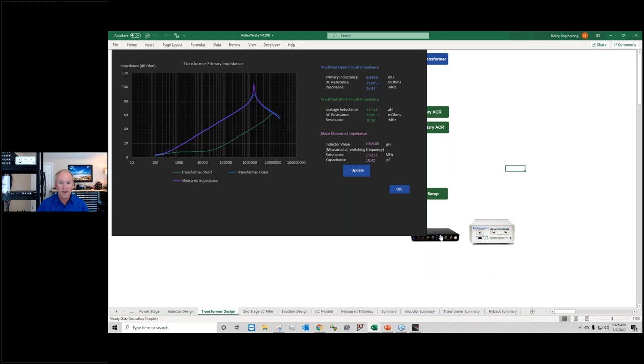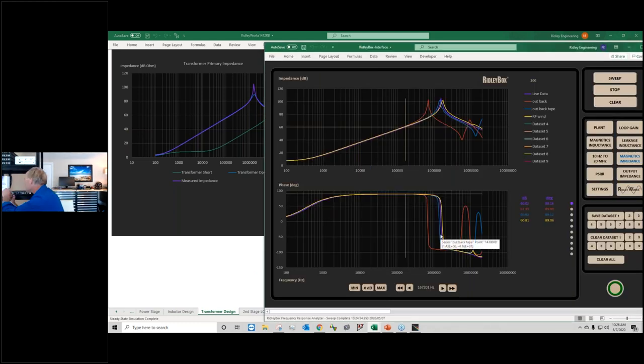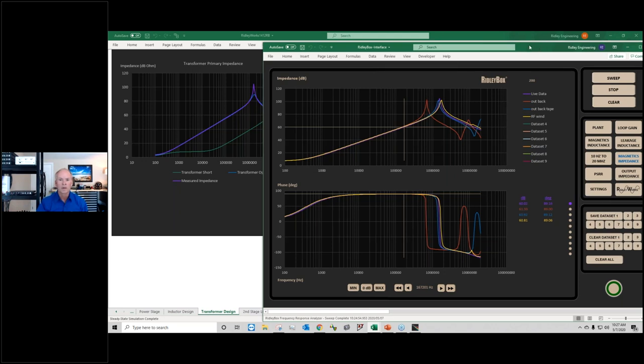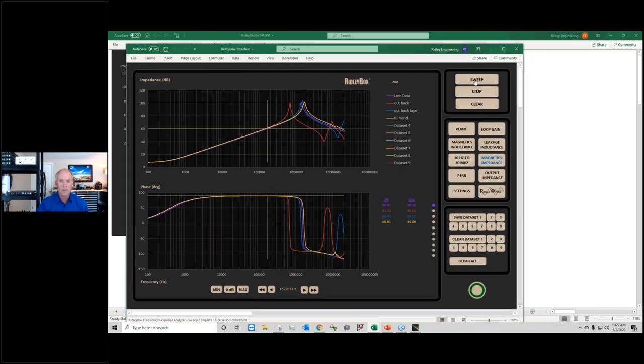And we go back to our analyzer again. And then we're going to take our secondary, short the two windings together. Okay, I'm going to use a different transformer here because I haven't got a good short on that one. Let me take my primary, secondary, short the windings on the secondary, and then come up. Okay. And sweep one more time. Sweep initiated. Okay.